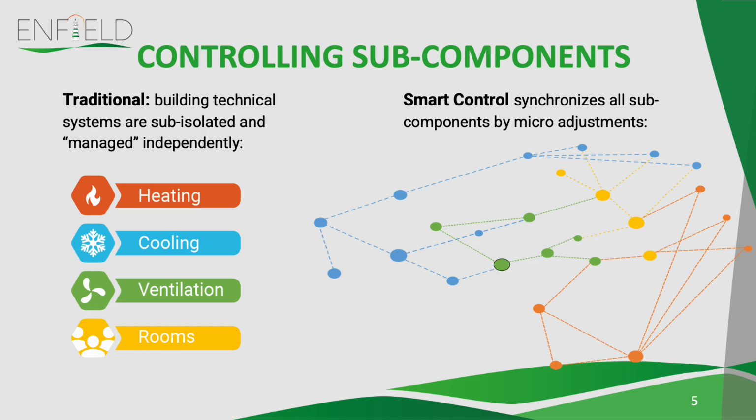But at 8-9 o'clock, the sun starts shining, the outdoor temperature rises, it is getting hot, and cooling starts working with full load. So you see, we have a double energy consumption just because two devices do not communicate with each other, and they don't take into account trends, predictions, weather conditions.